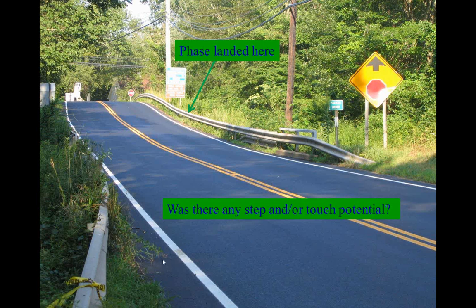The part that concerned me, because this happened around the corner from where I live, is that by the time I got there, the fire police had arrived. They had flagged that off. They had tied this flagging tape, and that's where they put the other piece. They put it over there. But fortunately for him, that recloser had already tripped the wires. And I asked him, how did you know it was safe? How did you know that recloser had already shut the power off? And he goes, "What recloser?" So we had to do a little training, and that was a very close call. We could have lost a fire police volunteer with that one if he'd have been a little quicker.